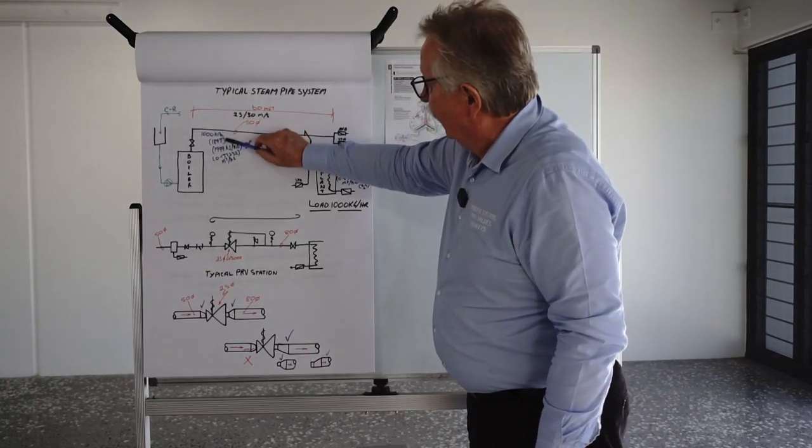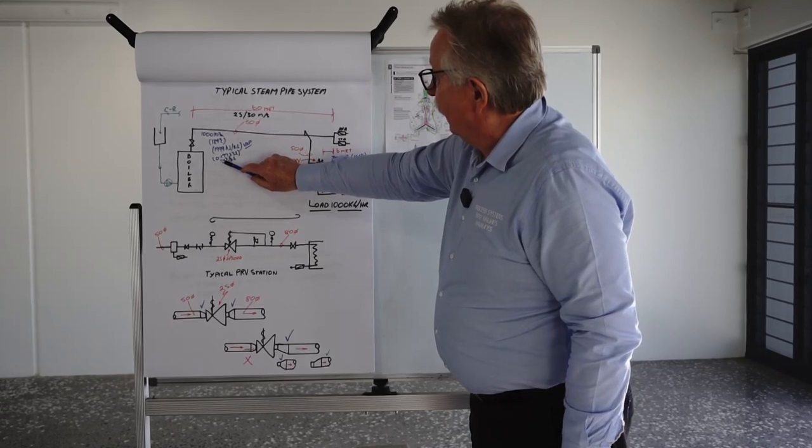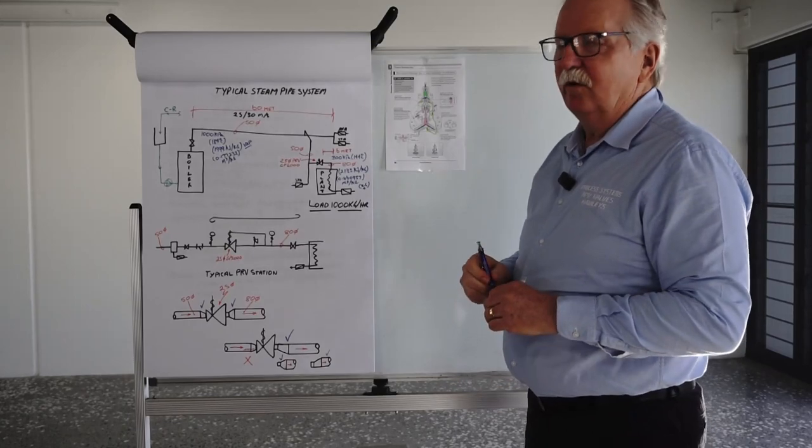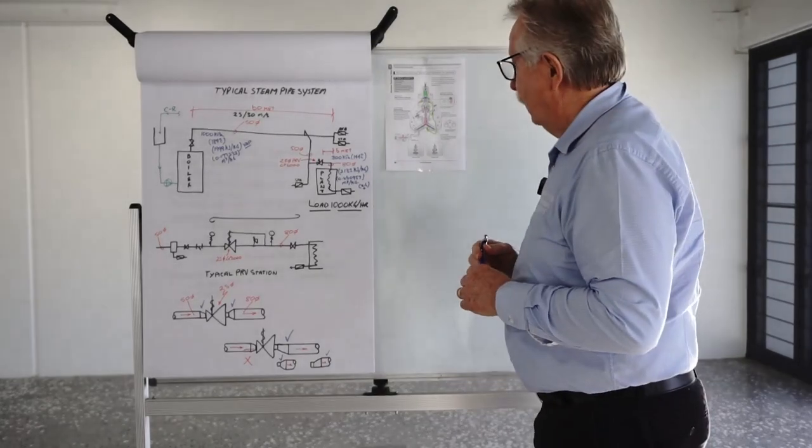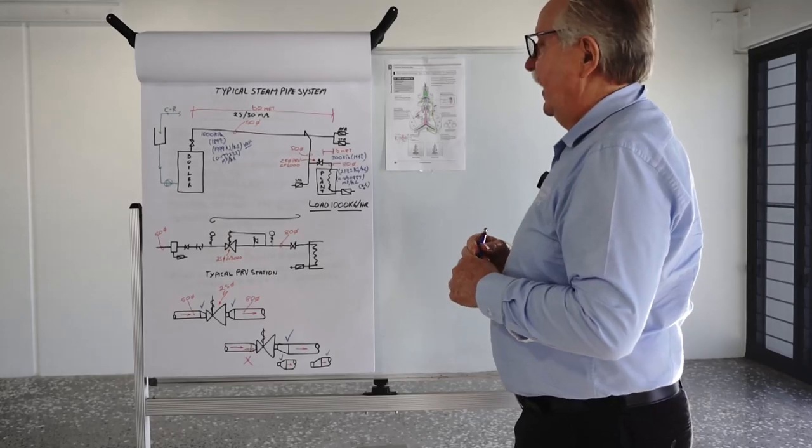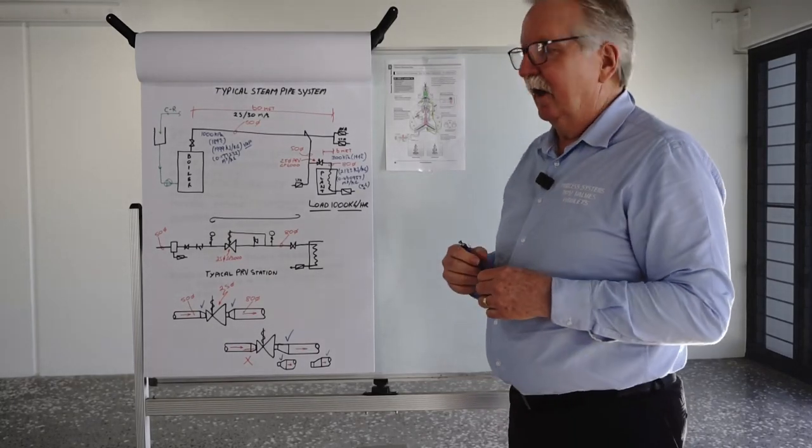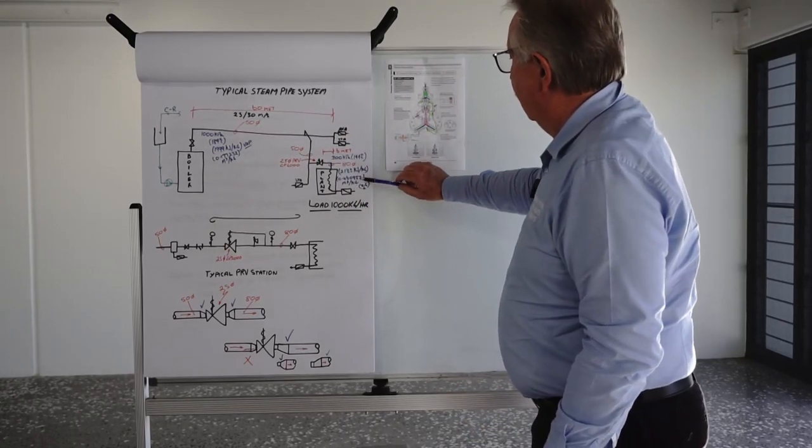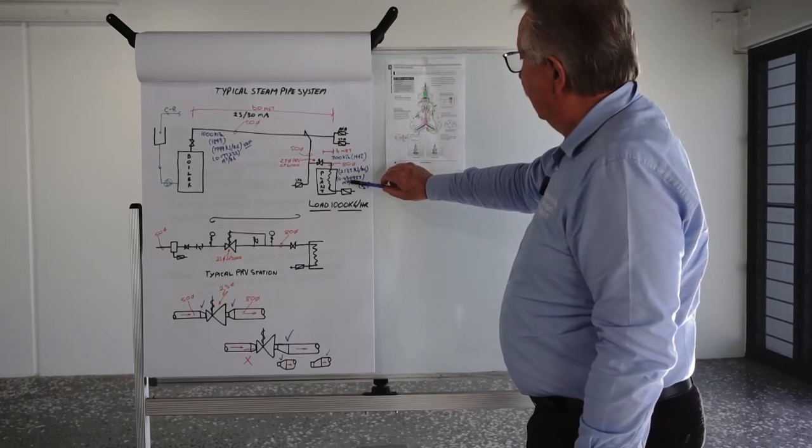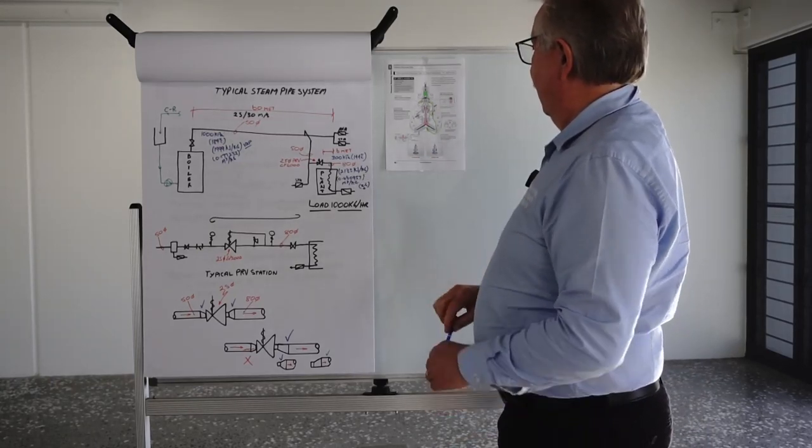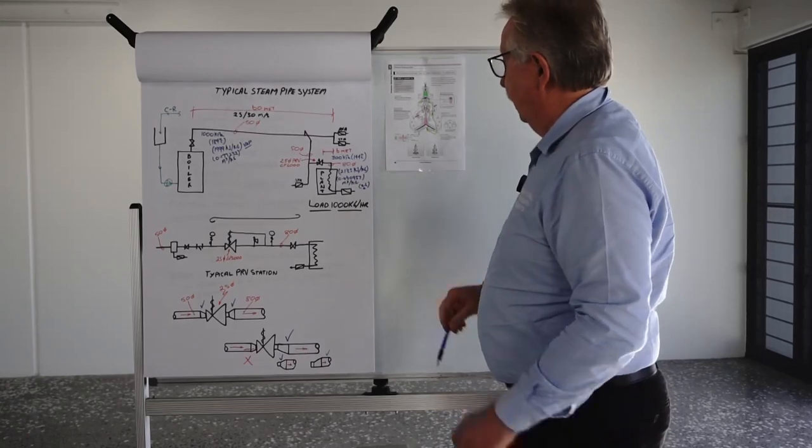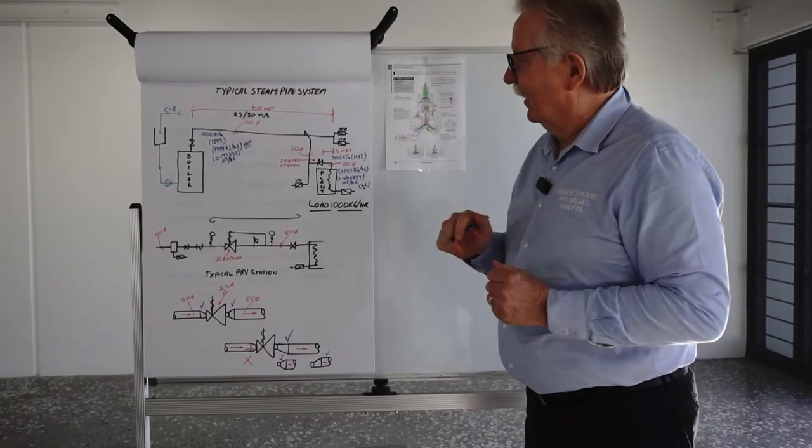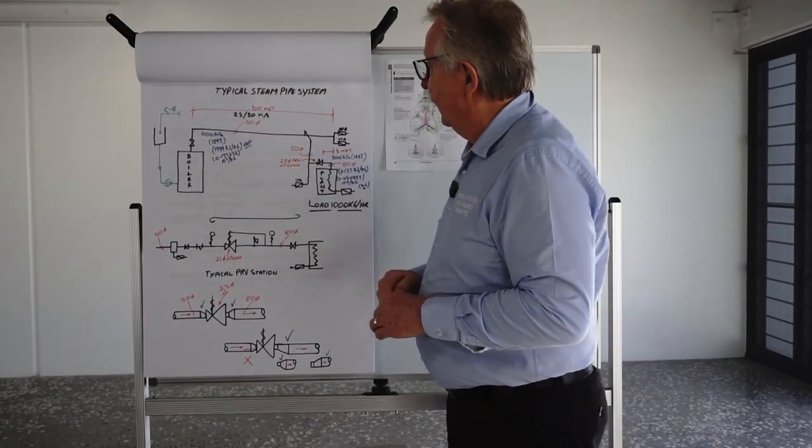In this case what we've got is a specific volume of 0.177232 cubic metres per kilogram. Again refer to the steam tables. The steam tables are a very important part of pressure reduction and identifying what you need to do and how you need to do it. If you look at the 300 kPa our specific volume is 0.460957 cubic metres per kilogram. It's almost 2.6 times bigger than the steam volume at 1000 kPa.